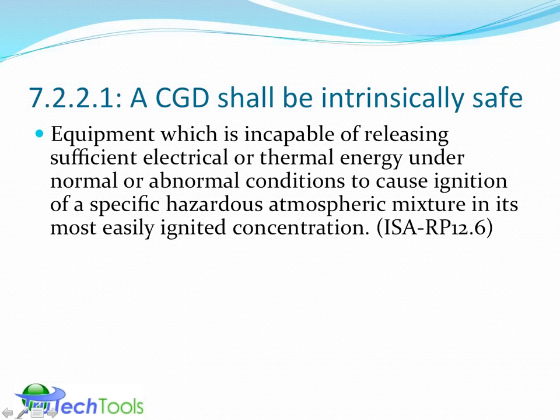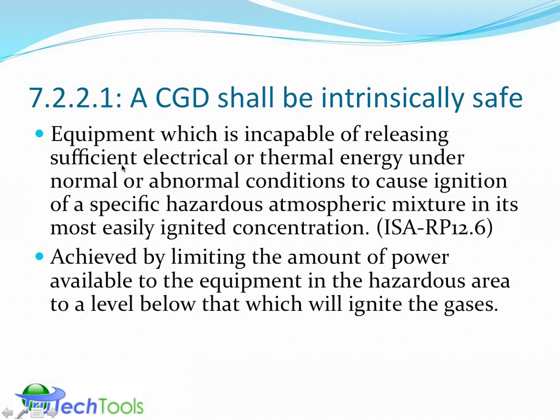This definition of intrinsically safe here is one which will help you understand. Basically, intrinsically safe means the equipment or the product, the meter, whatever, does not have enough energy in it under any kind of conditions, normal or abnormal, to cause ignition in a certain kind of atmosphere in its most easily ignited concentration. So it makes it ultimately a safe product that intrinsically, in and of itself, is safe to use in explosive atmospheres.